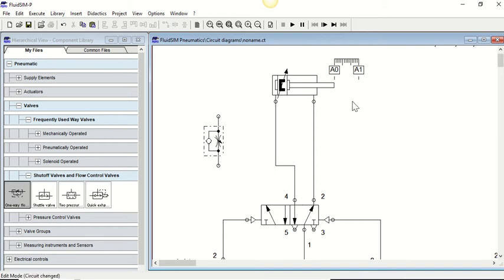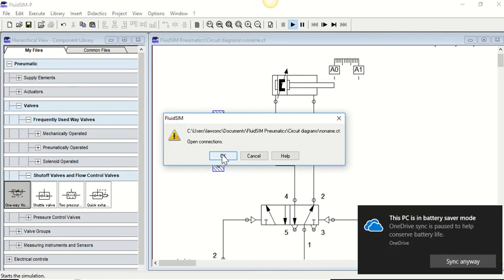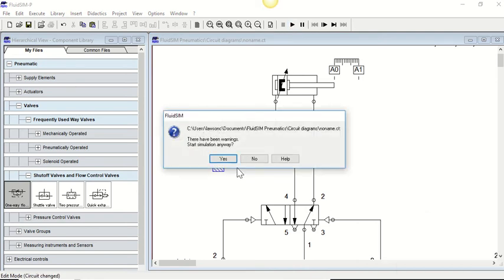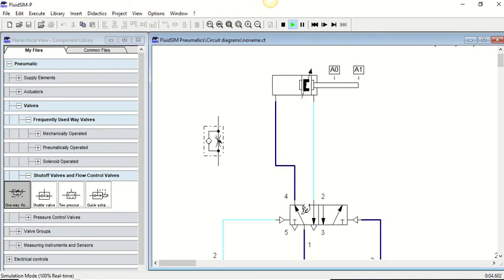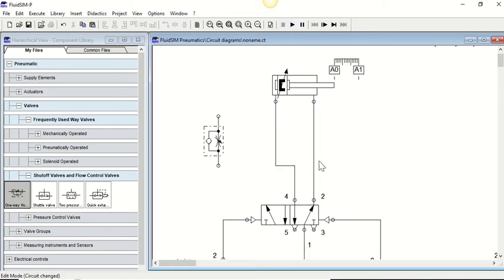So you'll see if I just operate this valve, don't mind that we have these errors because we haven't connected this component in yet. I just want to operate this valve, and you'll see that as air is flowing in, we're going into the cylinder, pushing it down, and then we're exhausting on this line here. So this is the exhaust line on the forward stroke. If we want to limit the forward stroke, this light blue line is where we're going to put the flow restrictor, because we usually meter out as the air is flowing out and exhausting. Okay, so let's just see that in operation.